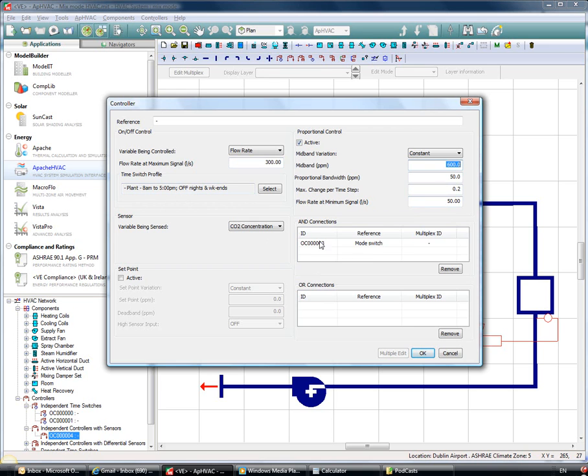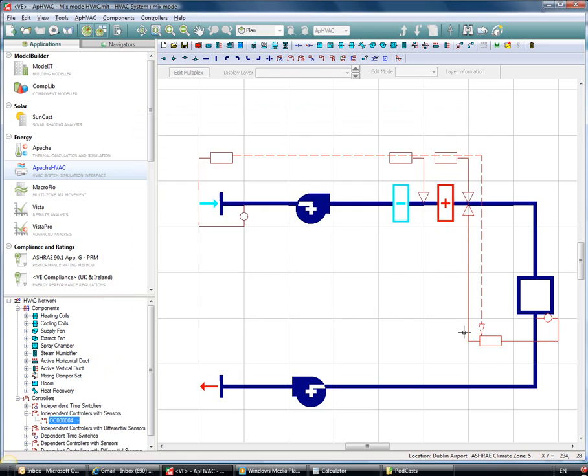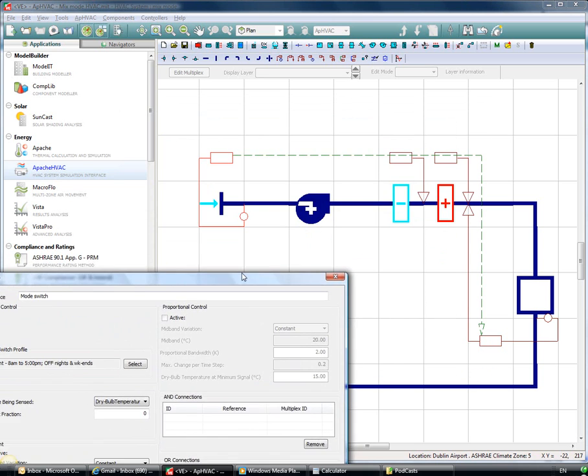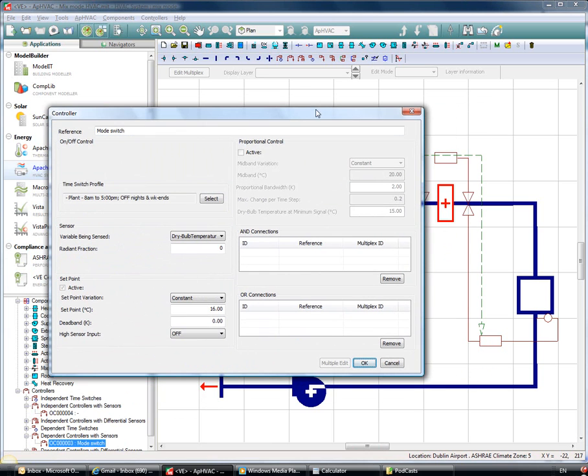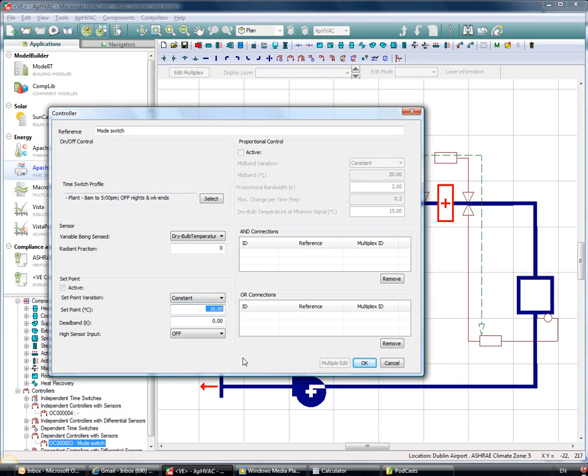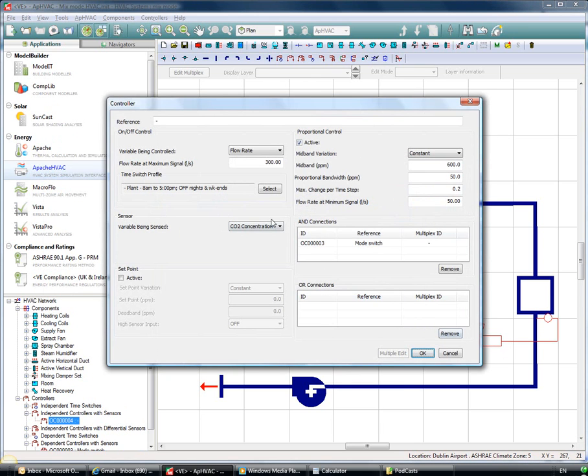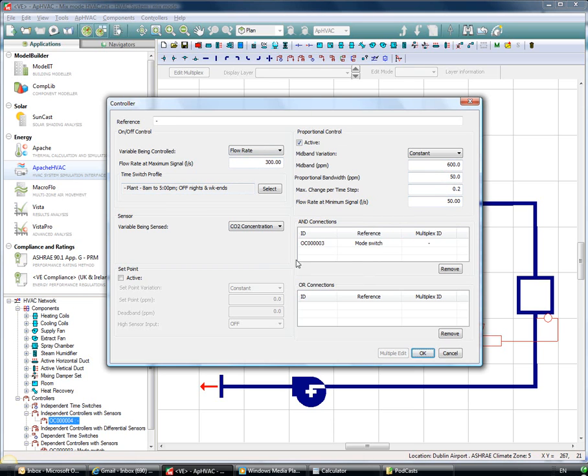What you notice as well is that there's an AND connection in there. And what that AND connection means, it's connected over here into this outside air sensor. I've got this sensor which is sensing the outside air ductwork there, and it's basically just, what it's saying is it's sensing dry bulb temperature between those hours which I've already stated, and it's sensing to see when the temperature is below 16 degrees C. And when that temperature is below 16 degrees C, that's basically linked in here and saying once the temperature is below 16 degrees C, this air flow can come on, this mechanical ventilation can come on and can modulate up and down according to the ppm within the space, CO2 levels within the space.